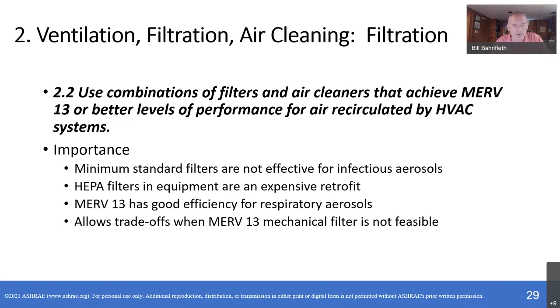Why is this important? The minimum standard filter is the MERV 8s that we find in minimum standards for commercial buildings aren't effective for infectious aerosols. HEPA filters, which some were trying to make a requirement for central air distribution systems, are not feasible and an expensive retrofit. MERV 13 has a good efficiency for respiratory aerosols, and this approach allows trade-offs when that can't be done. Next.